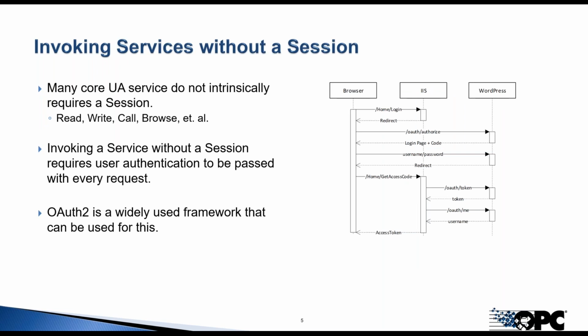Now, if you've never done any work with OPC UA, you will realize fairly quickly that everything seems to be based on the concept of a session. You create a session, then after that you can do all of the other stuff you might want to do: read, write, subscribe, you name it. And this is heavyweight. It's got a bunch of state that's being stored on the server, which creates potential issues for some applications.